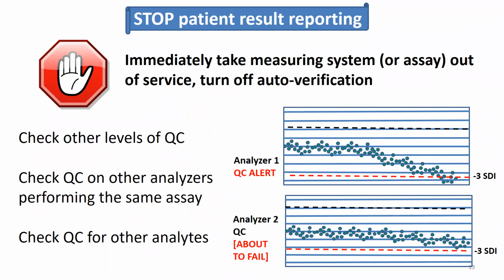The second step is to quickly determine the scope of the problem. Check the other levels of QC for that assay to see if they're affected. Check QC for other analytes on the same instrument to see if they're also affected, which could suggest a global instrument problem and that the entire instrument needs to be taken offline. Also check QCs on other instruments to see if the problem is affecting multiple instruments.